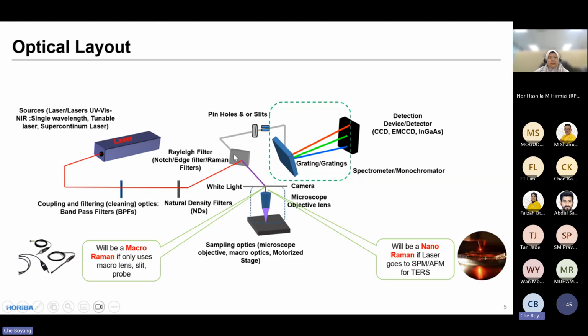this light will go through the filter and reach the spectrometer part. Just in front of the spectrometer, we have a pinhole, whose size you will be able to control. Later I will introduce the function of this small hole. Once it enters the spectrometer part, it will meet several mirrors that change the direction of the light. The light will finally be reflected to the grating. The grating is the key component inside the spectrometer, and it helps you disperse your signal. Your signal will be dispersed based on wavelength, so that your detector will be able to collect all the signals at different wavelengths. The detector we use is usually a CCD, so that you can capture multiple spectra at the same time. So this is how a Raman microscope works. It goes through all different types of optics inside and finally gives you the signal.